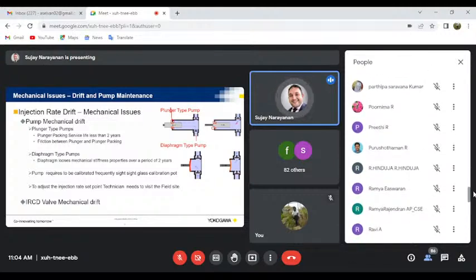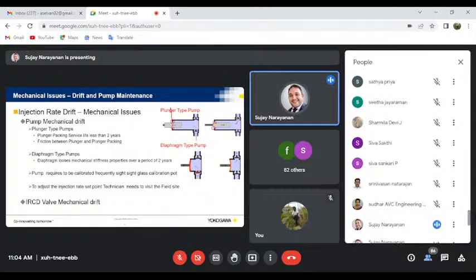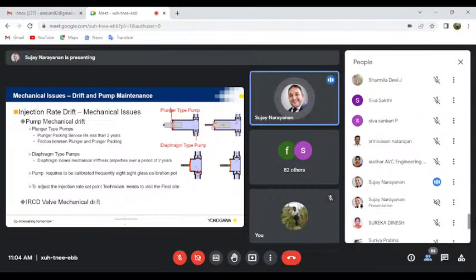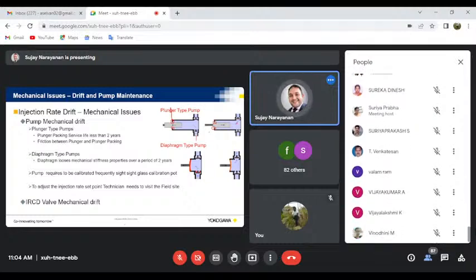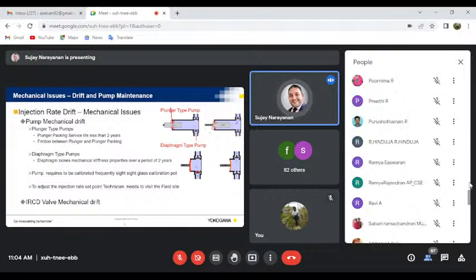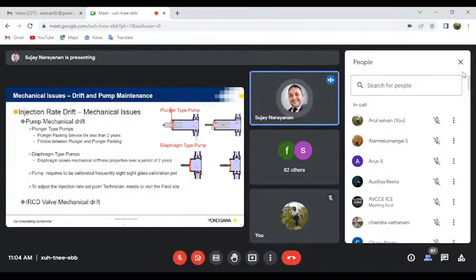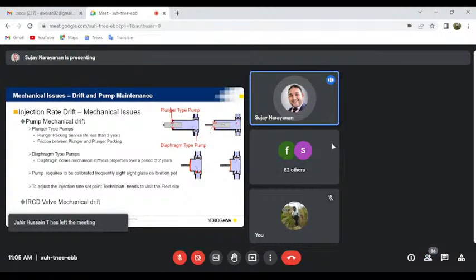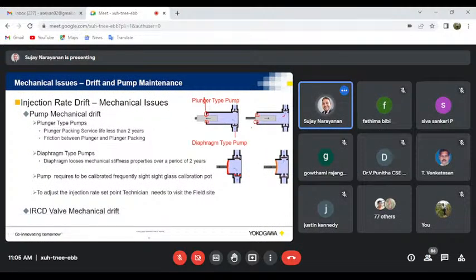Moreover, if there are any solid impurities building up in these valves over here, then they do not fully close, and that will also create undesired drifting issues. Number one, that is because of the mechanical factors. Number two, these chemicals are generally a little bit viscous; the viscosity is higher than water. And these chemical tanks are placed outside. In the desert, in the daytime in summers you have 47 or 50 degrees, and at night at least 28 or 30 degrees. So you have more than a 15 degree delta, and because of the ambient temperature fluctuation between summer and winter, daytime and nighttime, the viscosity of the chemical changes.